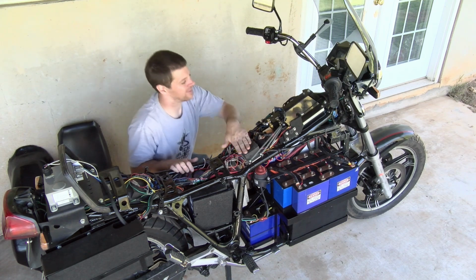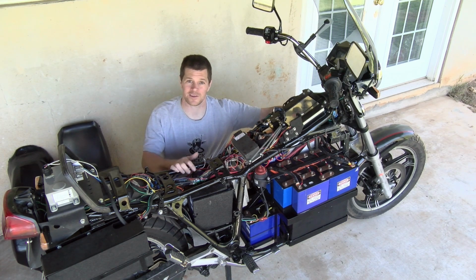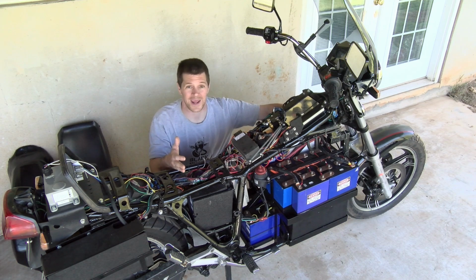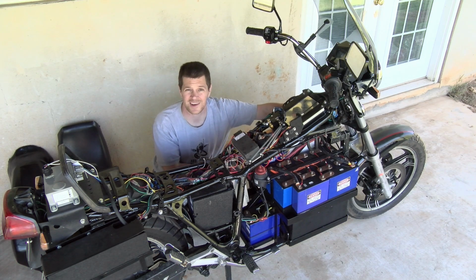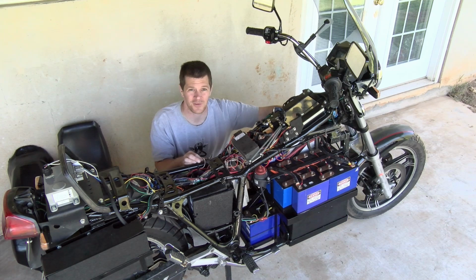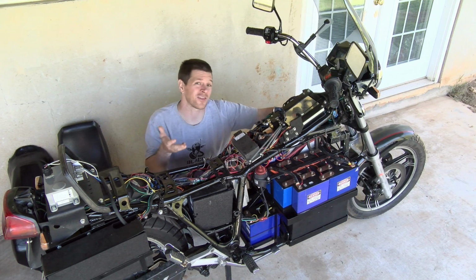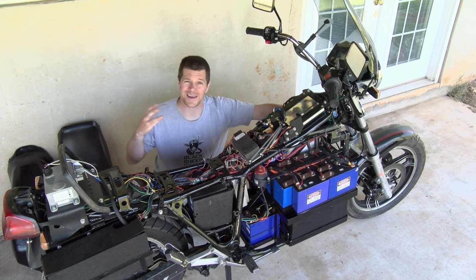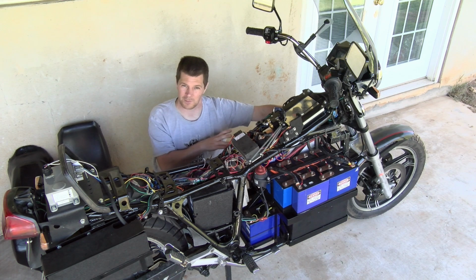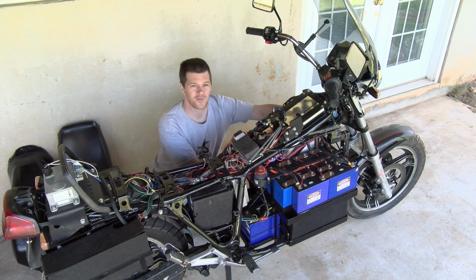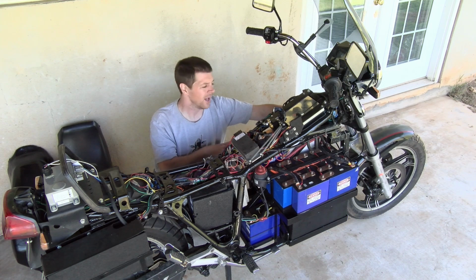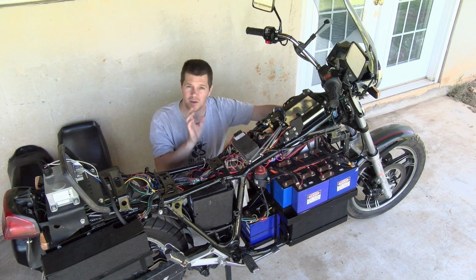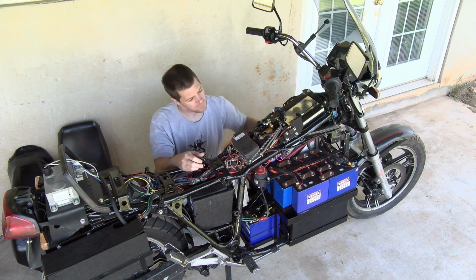Before it gets to this, hidden under here is, as I said earlier, a 600 amp fuse. Now, my motor takes 750 amps, so why a 600 amp fuse? Well, fuses have a thermal curve, and an 800 amp is just too much. For a 750 amp peak motor, the 600 amp fuse seems to be just about right.